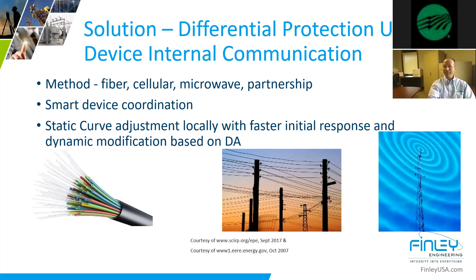Manufacturers have been telling us for a while that if you had smart devices with controls, you could—and of course the perfect example is a radial feed or loop feed, not an extended lateral that doesn't go anywhere—if you've got a loop potential, you can have devices coordinated and talking to each other in such a way that you can isolate segments, feed from the other, back-feed from the other way, and minimize the impact to consumers.